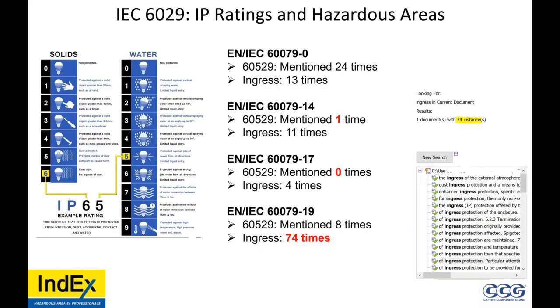So, ingress protection in hazardous areas. We get told quite a bit that ingress protection has nothing to do with hazardous areas. Well, that's interesting. The word ingress is mentioned 74 times in the repair standard 60079-19. It's also mentioned 24 times, the 60529 standard, within the general requirements of 60079-0. So -0 is for manufacturers, -19 is for repairers, repair facilities. The manufacturer perhaps does the repair.